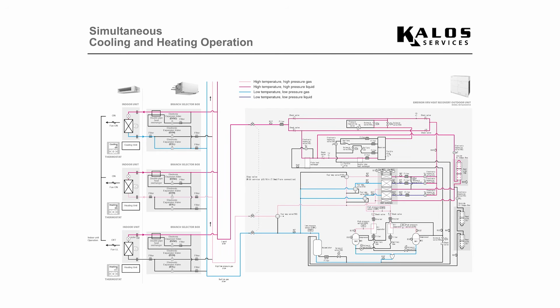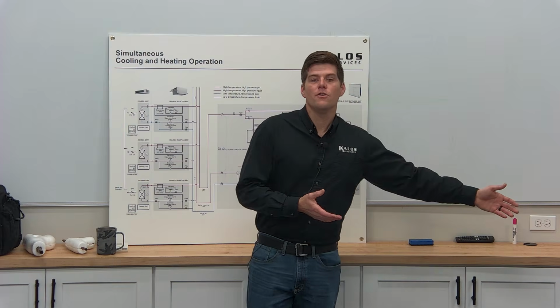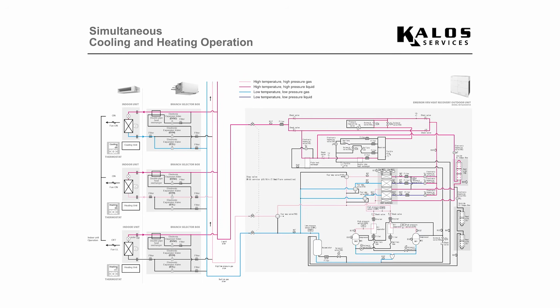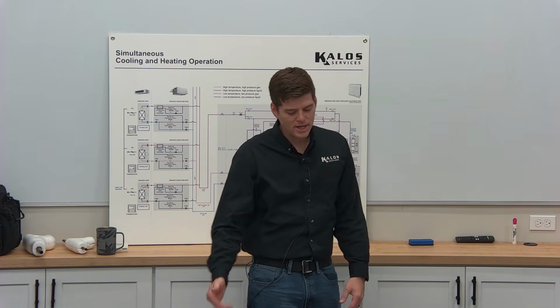The picture you see here in front of me is pulled from Daikin's slide deck of residential systems, right? I am showing you that the things we check on a residential system, everything you see on this screen, is the same thing that is in a VRF system. Same thing that's in a VRV system. We haven't changed it. There's a few extra components between the indoor unit and the outdoor unit. There's a few extra components between the compressor and the condenser, between the condenser or outdoor heat exchanger and leaving the actual outdoor unit. But it's all the same concept, guys.